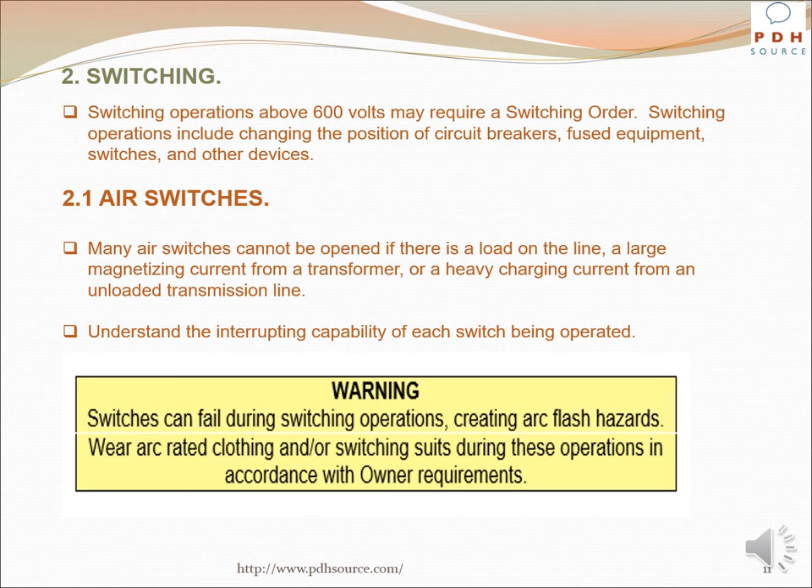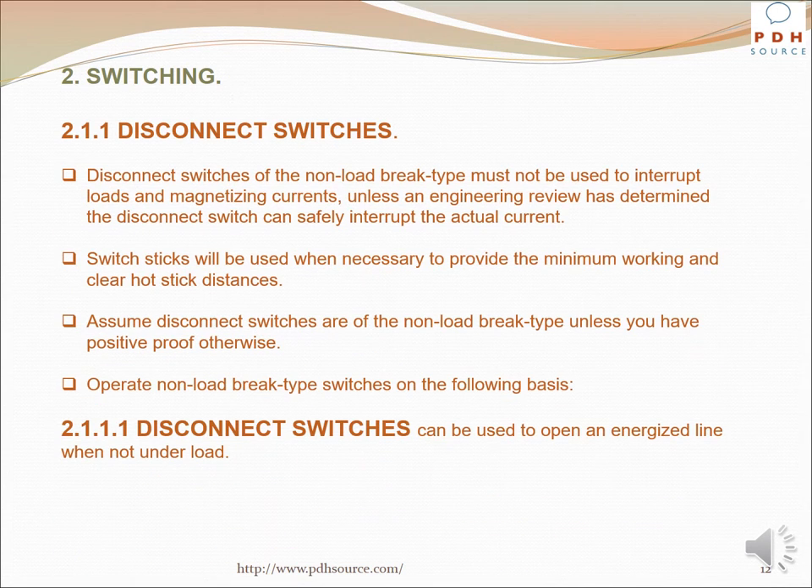Many air switches cannot be opened if there is a load on the line, such as a large magnetizing current from a transformer or a heavy charging current from an unloaded transmission line. Understand the interrupting capability of each switch being operated. Warning: switches can fail during switching operations, creating arc flash hazards. Wear arc-rated clothing and/or switching suits during these operations in accordance with owner requirements. Disconnect switches of the non-load break-type must not be used to interrupt loads and magnetizing currents unless an engineering review has determined the disconnect switch can safely interrupt the actual current.